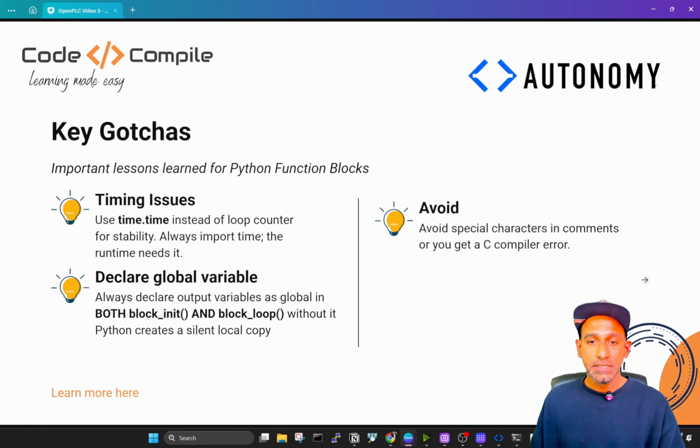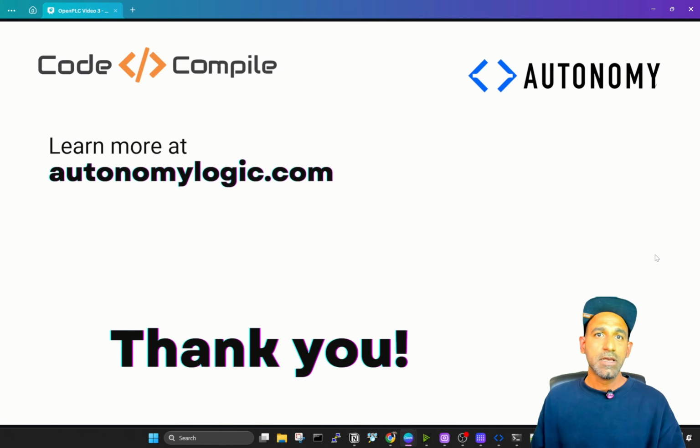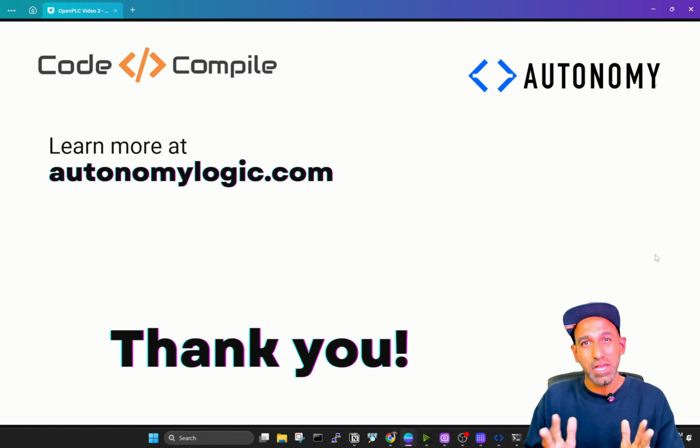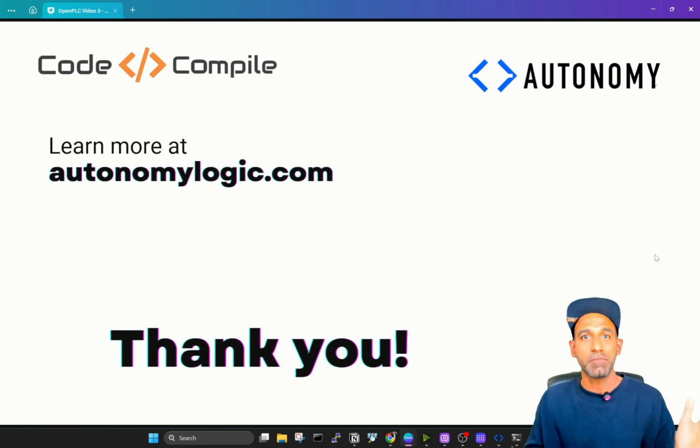All right. So most of the time, the question comes up: when to use Python, when to use structured text, when to use C++. I would say use Python for cloud communication, JSON formatting, statistical calculations, HTTP and MQTT communications, anywhere which will make your code easy because you can use standard libraries, right? And you can use structured text for deterministic control logic, for timing, for sequencing, for interlocks.